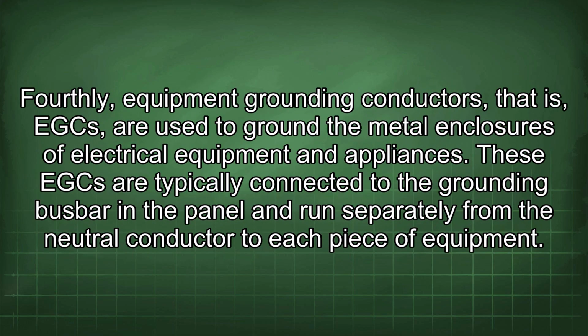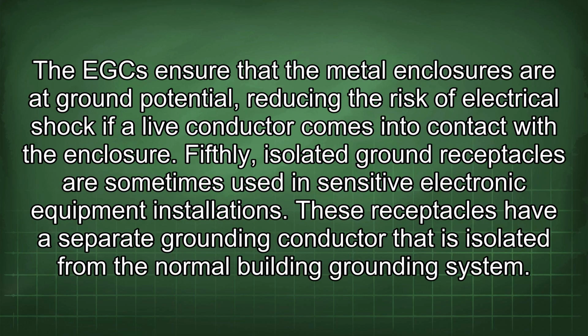Fourthly, equipment grounding conductors, that is, EGCs, are used to ground the metal enclosures of electrical equipment and appliances. These EGCs are typically connected to the grounding busbar in the panel and run separately from the neutral conductor to each piece of equipment. The EGC ensure that the metal enclosures are at ground potential, reducing the risk of electrical shock if a live conductor comes into contact with the enclosure.